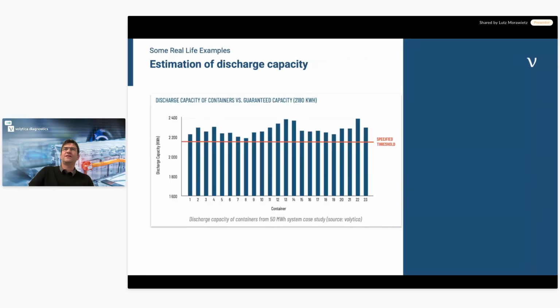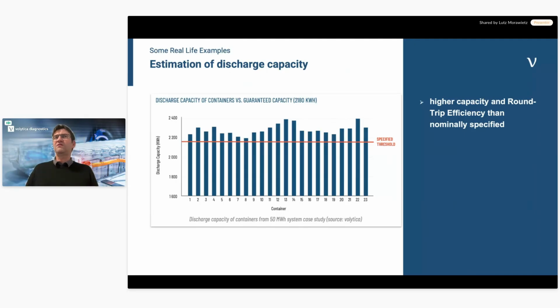The first example is a standard capacity test, which everyone should do with every container or every part being investigated. We have this example from a large battery storage system, 50 megawatt-hour system, 23 containers. In this diagram, the orange line shows the threshold, and every container is above it. So what is the finding? Everything is fine - true. But there was a higher capacity and round trip efficiency than nominally specified, which is good. You can be happy if every container is bigger than what's specified by the manufacturer.